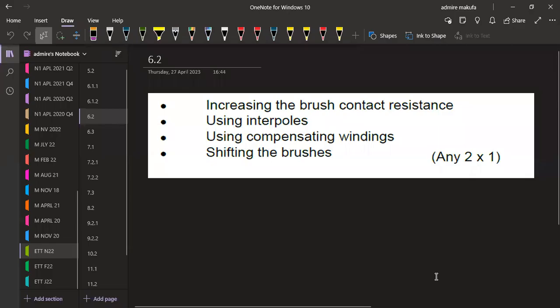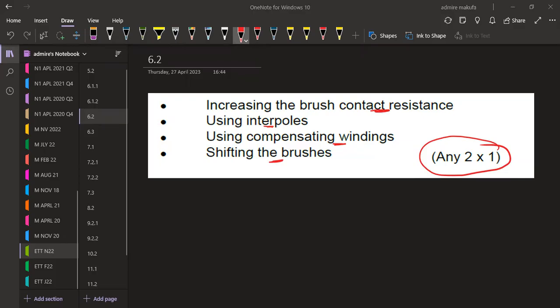So we've got a lot of methods that we can have, but just a few. We can reduce this sparking by increasing the brush contact resistance, using interpoles, using compensating windings, shifting the brushes. So just any two from these ones can be based on your answers. So just have to pick any two. So if you have got any others that you know about or that you can help us with, make sure that you mention them on the comment section so that we can also add for more revisions.